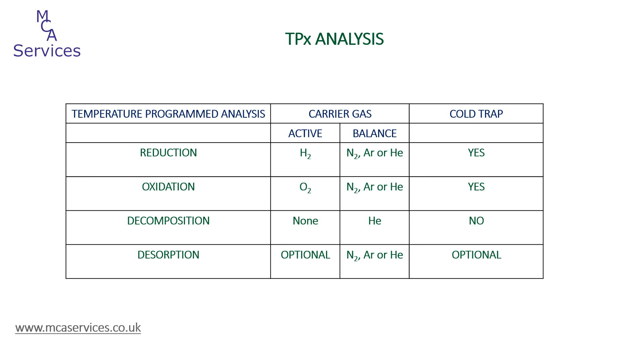However, if the decomposition product is corrosive, we should really consider using a cold trap or, perhaps better still, replacing the TCD with an alternative detector which won't be susceptible to damage. With temperature programmed desorption, our active gas is the molecule we want to investigate. A sample could be exposed to a flowing stream in situ, either from a gas supply or from the built-in vapour generator. An inert balance gas is used, and a cold trap isn't usually required because we're aiming to detect the desorbing species at the detector. But care must be taken when deciding whether the desorbing species will interfere with the TCD or damage it in any way.